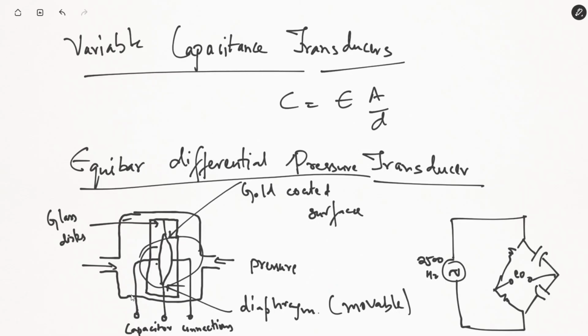With equal pressure applied to both parts, if it's in normal position, if pressure is coming from both sides, the diaphragm will be in the neutral position, and at that time the bridge will be balanced. We calibrate this device so that if there is equal pressure from both sides, the diaphragm will be in its neutral position and the output voltage will be zero in that case.